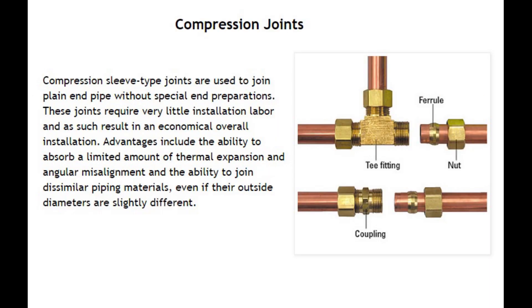Number 7: Compression Joints. Compression sleeve type joints are used to join plain end pipe without special end preparations. These joints require very little installation labor and as such result in an economical overall installation. Advantages include the ability to absorb a limited amount of thermal expansion and angular misalignment, and the ability to join dissimilar piping materials, even if their outside diameters are slightly different.